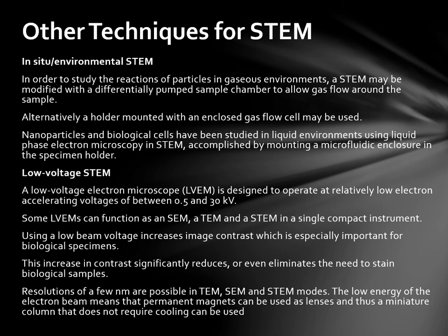Then we also have environmental STEM. In order to study the reactions of particles in gaseous environments, a STEM may be modified with a differential pump sample chamber to allow gas flow around the sample. Alternatively, a holder mounted with an enclosed gas flow cell may be used. Nanoparticles and biological cells have been studied in liquid environments using liquid phase electron microscopy in STEM, accomplished by mounting a microfluidic enclosure in the specimen holder. Then we have low voltage STEM. A low voltage STEM electron microscope is designed to operate at relatively low electron accelerating voltages of between 0.5 and 30 kV. Some LVEMs can function as a TEM, SEM and STEM in a single compact instrument. Using a low beam voltage increases imaging contrast, which is especially important for biological specimens, significantly reducing or even eliminating the need to stain biological samples.